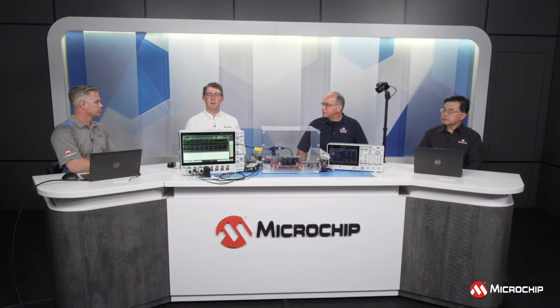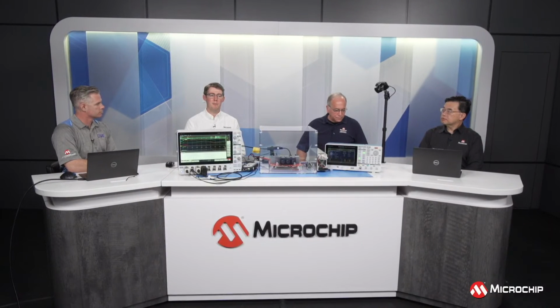In general, single-ended probes are much better in terms of their DC gain accuracy relative to high voltage differential probes. They also tend to be less expensive than differential probes, so it is possible to use them in double pulse testing. The one very critical consideration to keep in mind is that they should only be used in reference to the low side FET, as that low side FET can be ground referenced.